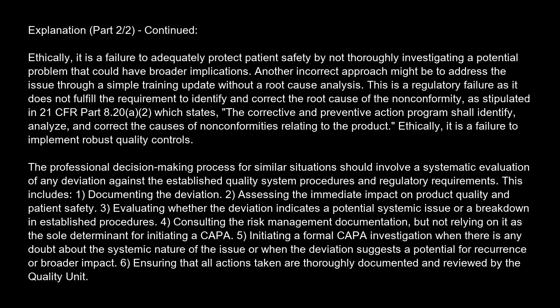Another incorrect approach might be to address the issue through a simple training update without a root cause analysis. This is a regulatory failure as it does not fulfill the requirement to identify and correct the root cause of the nonconformity, as stipulated in 21 CFR Part 820.100(a)(2), which states, "The corrective and preventive action program shall identify, analyze, and correct the causes of nonconformities relating to the product." Ethically, it is a failure to implement robust quality controls.